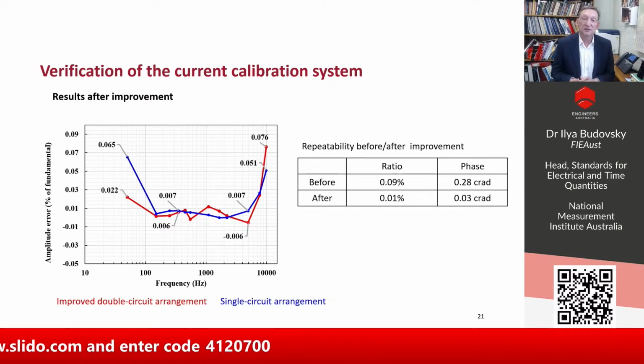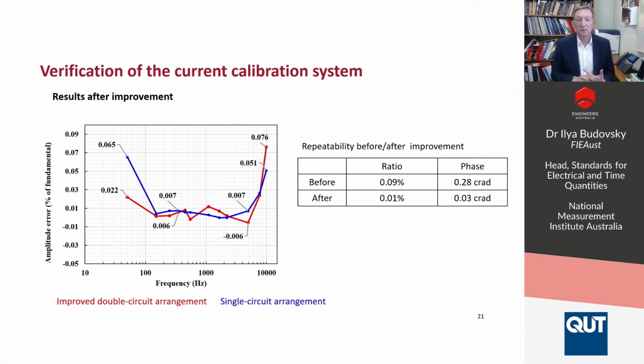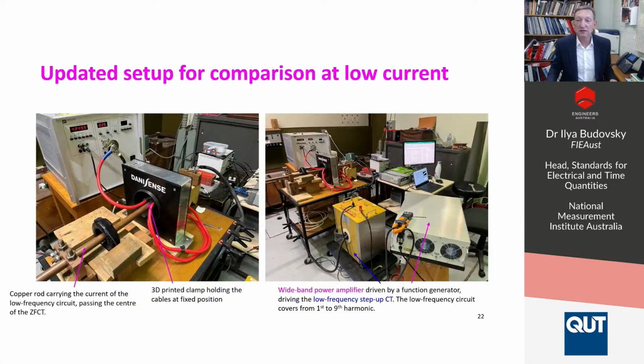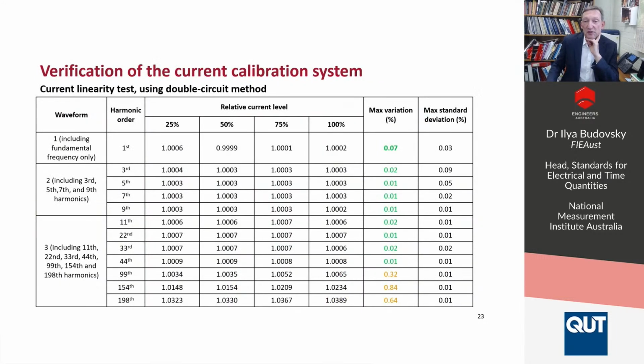We also reduced the standard deviation or repeatability to around 0.01% or about 0.03 centiradians, which is more than enough for this job. And this picture shows this improved arrangement. The final piece of work for the current system is to test its linearity. We've done it by doing a linearity test in a double circuit arrangement, and the results are presented here. We did it for some groups of harmonics, and the results are excellent up to the 44th harmonic, and they are acceptable for all other harmonics, but we're working on making them excellent as well.